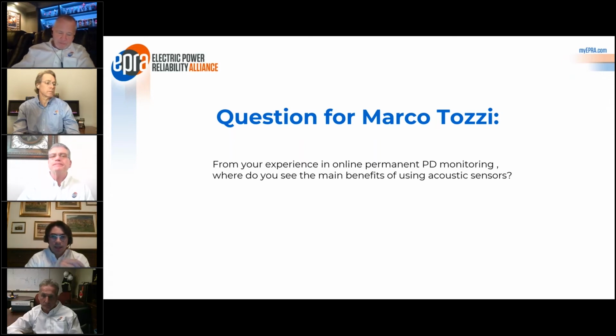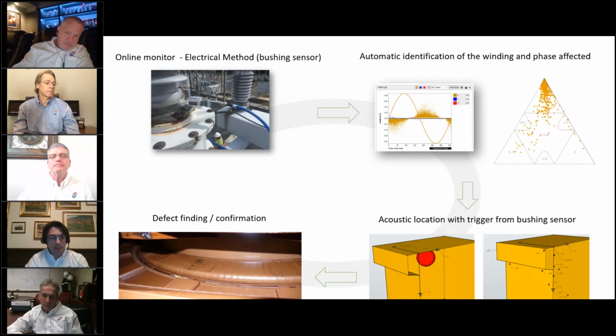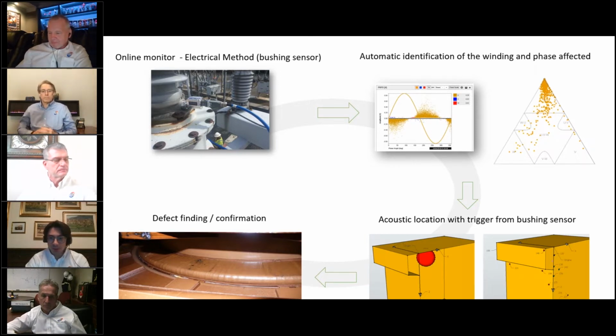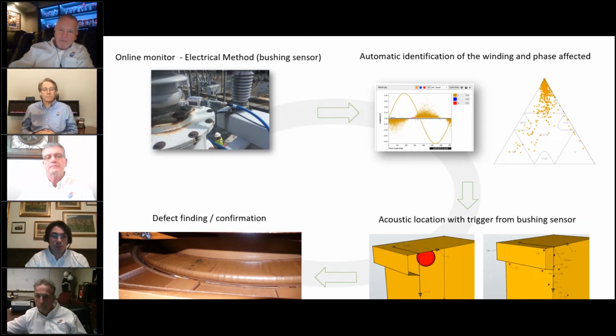Okay, so I have a slide here to help answer this. This is a real case—I guess this is the best way to answer, showing something from the real field. This is a 63 MVA distribution transformer in Europe. This transformer was fairly new, only 2 years of life, and it was already gassing. When I say gassing, I mean it was primarily showing some hundreds of ppm of hydrogen and just a little bit of acetylene. The OEM's answer in this case was, no worries, it's stray gassing—which is quite a common answer sometimes. Basically the answer is just wait, it will settle down. But if there's even a little bit of acetylene, it can't be stray gassing.